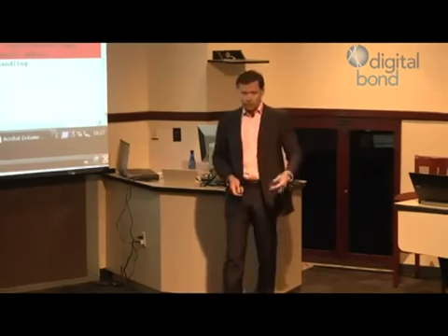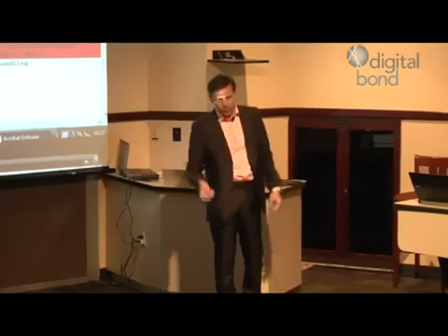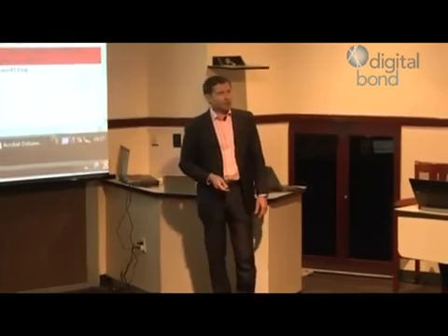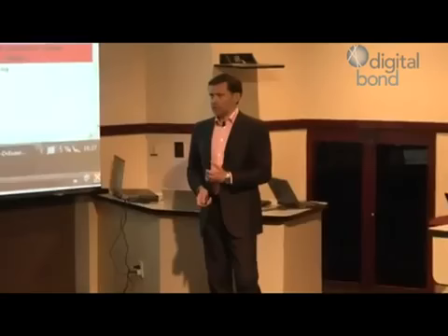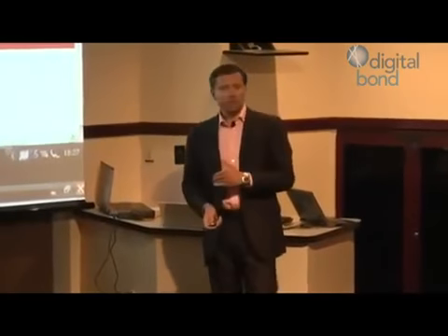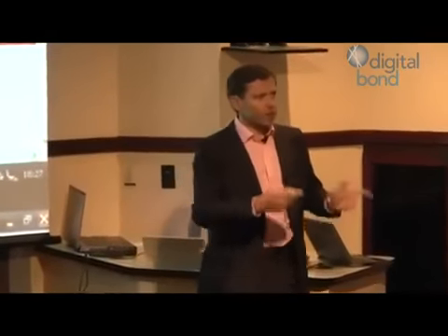Funny thing is, and I'm pointing this out because we discussed the vulnerability stuff just earlier, this could be fixed easily. The vendor could have fixed this a year ago by just making the input process image read-only. They were just treating it as another block of memory where you can dump data in, just using a block move. This could have been fixed a year ago, but the vendor chose not to. The vendor chose to be silent about this. Well, funny thing is, DHS also chose to be silent about this.